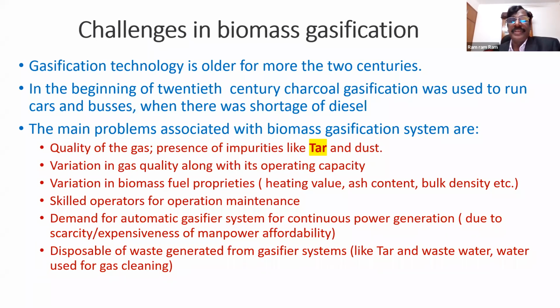Next, the variation in gas quality along with operating capacity. The gasification reactor works at a certain temperature. When you burn more biomass, the temperature is high. When you burn less biomass, the temperature is less. The gasifier capacity is given, let us say, for a 100 kilowatt system that will consume about 100 kg per hour. The same generator, if you operate at 20 or 30 kilowatt, comes to a 20 kg per hour system. So if a 100 kilowatt system is operated at 20 kg per hour, the reactor temperature falls down like anything, then the tar production increases and the gas quality is affected. So the quality of the gas is directly proportional to the operating capacity rate of the system.